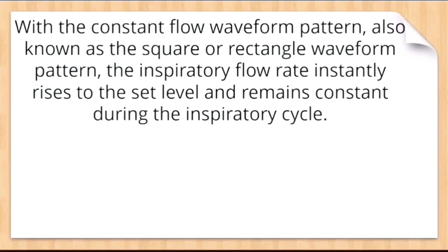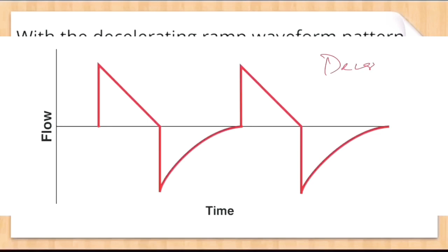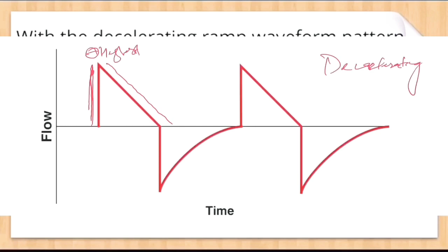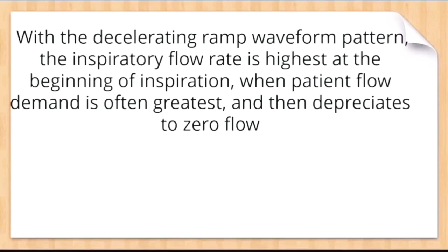Now the other waveform pattern is decelerating. With the decelerating ramp waveform pattern, the inspiratory flow rate is highest at the beginning of the inspiration when the patient flow demand is often greatest, and then it depreciates to zero flow. You can see in the figure, the inspiratory flow is highest at the beginning, when the patient flow demand is often greatest. Then it depreciates to the zero flow. So these are the two waveforms that can happen when you have kept the flow as a target. You'll either select a square or rectangular waveform pattern, or you can select the decelerating ramp pattern. Okay, is it clear?